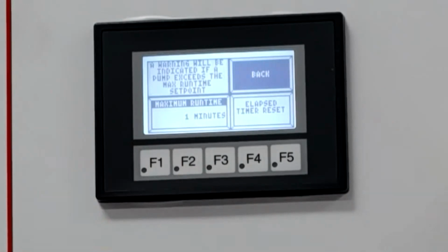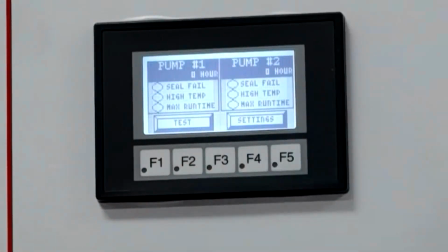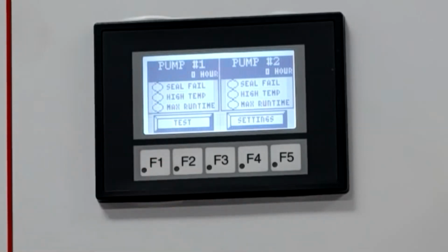The other one that we've added here is this runtime alarm. I have it at 1 minute for demonstration purposes, but typically we'll set that to 5, 10, 15 minutes, something of that nature. Basically what that's going to do is monitor every time a pump runs, how long it's been on. And if we hit the setting, we're going to get this max runtime alarm here, and that's going to give that alarm out to the building automation: hey, the pump's been running for an extended period. It doesn't shut it off because we'll have those massive rain events where we may actually need them to run that long, but it is a heads up to say, hey, the pump's been running that long. So that can help protect the pumps, protect the system.